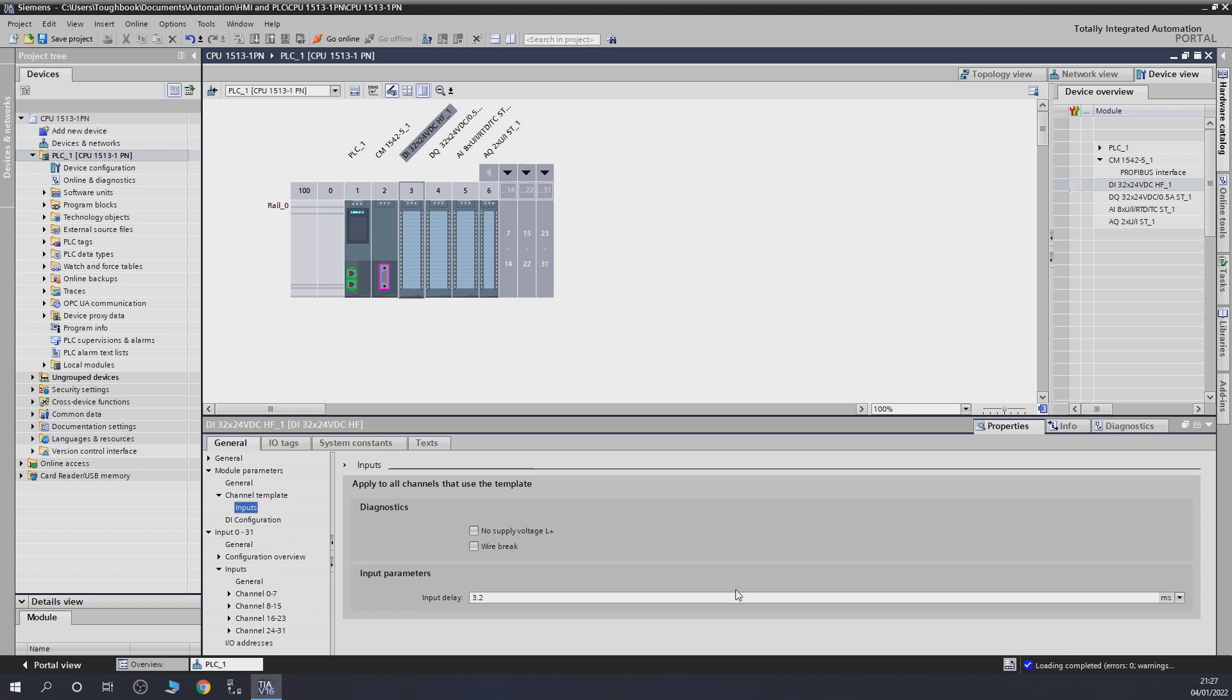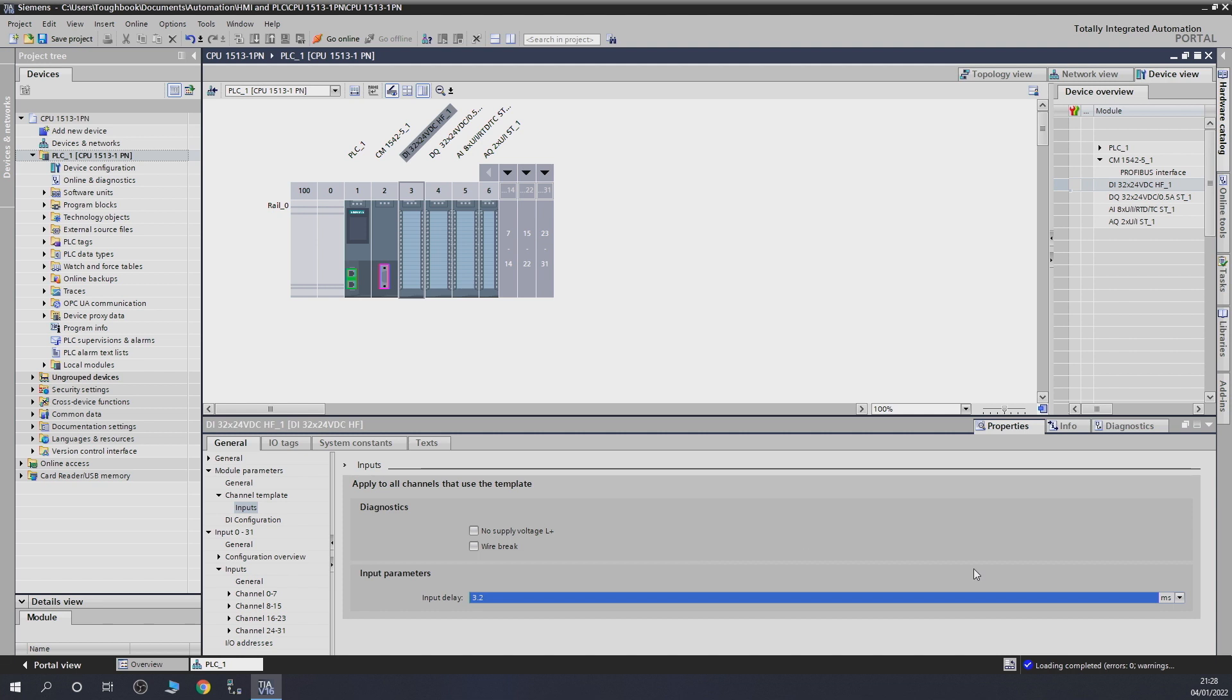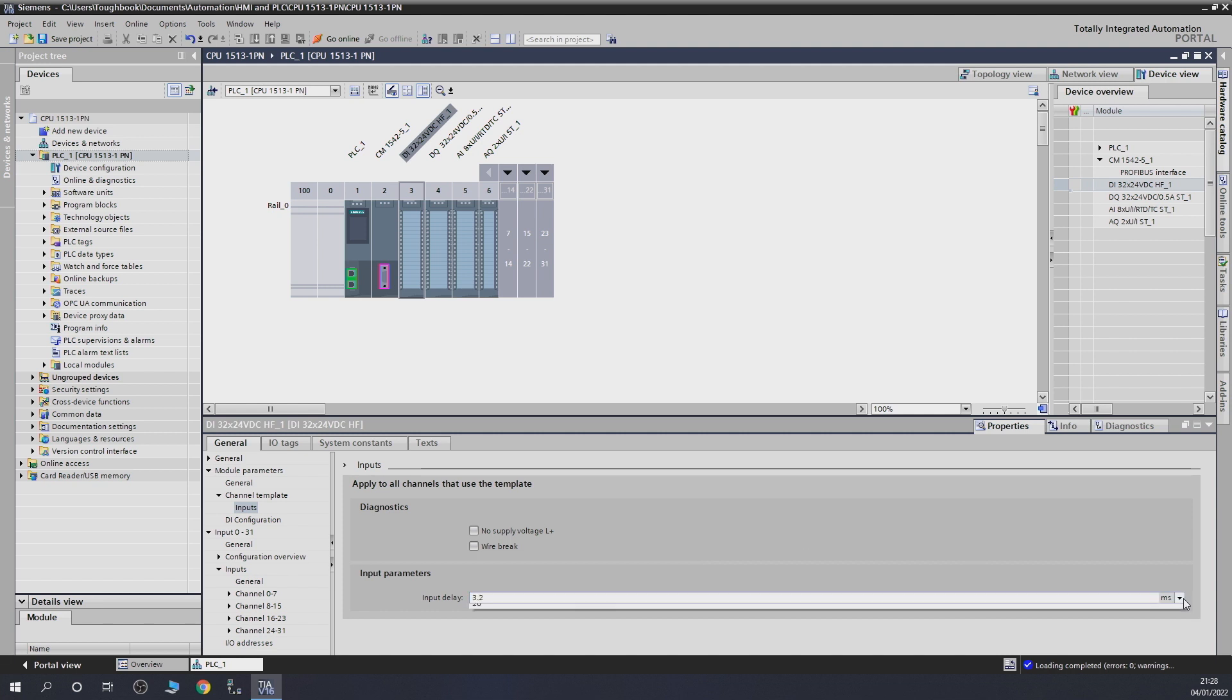Another thing I want to mention is you can see the input parameters, there is input delay. This is one of the cards where you are able to adjust your input delays. The reason you have those input delays is to stop what they call the signal toggling. So basically when you click the button, sometimes you can accidentally initiate two signals and all sorts of different things can go bad. So Siemens has implemented that the standard template they have has a 3.2 milliseconds.